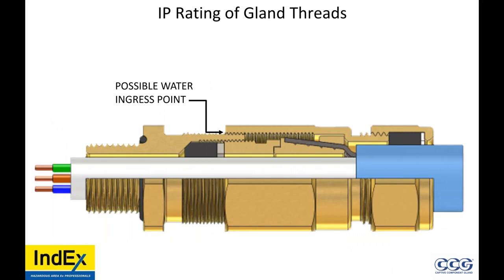When we talk about IP ratings of glands, most people, all they talk about is these threads, yeah? These threads into the entry into the equipment. Now, the problem is many manufacturers don't consider these threads, these threads, these threads. This IP rating right here, or ingress protection, is covered on the cable gland, on the cable, because it has this back IP seal kind of here, yeah, that sealing ring. But these other threads are not always considered, or the manufacturer has made it where it's not practicable. One manufacturer has a deluge seal that you must pull. I can say that 99% of all glands across all sites and all pictures of that gland, nobody pulls the deluge seal.